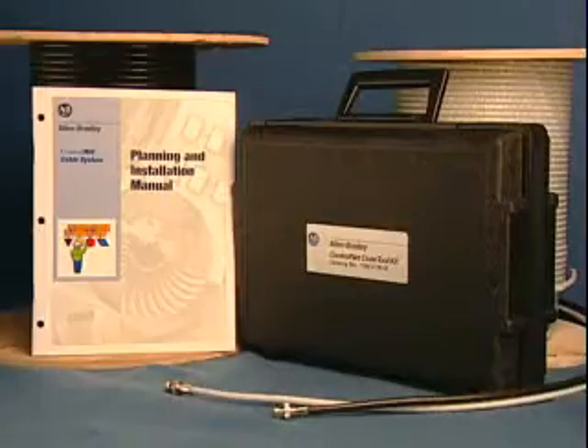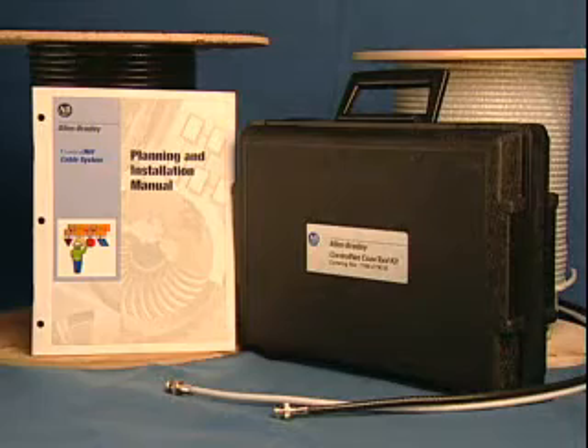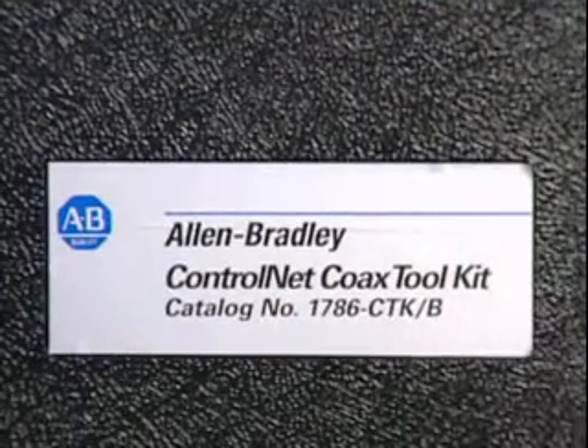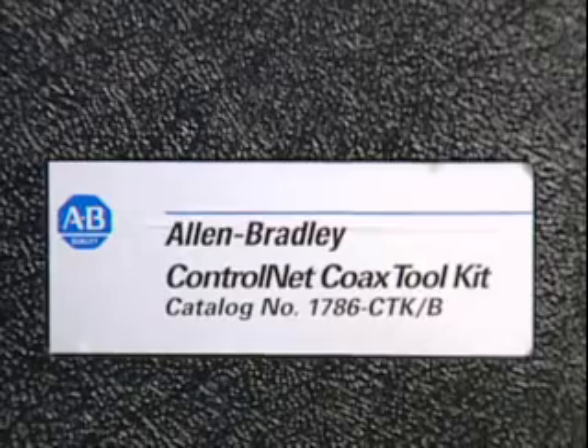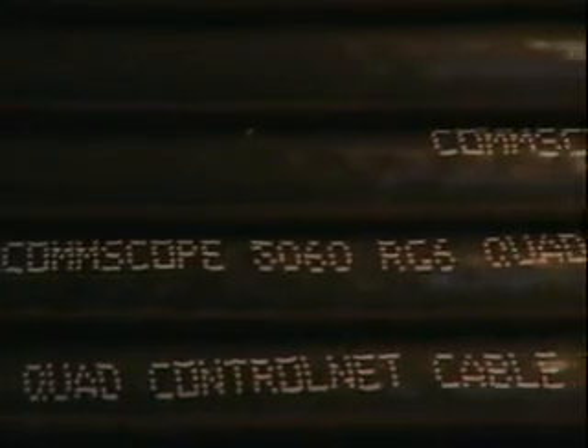As an authorized manufacturer of cable for Allen Bradley, we'd like to demonstrate the proper connectorization procedures for ControlNet cable. We will be using the Allen Bradley ControlNet Toolkit, catalog number 1786-CTK/B, and CommScope non-plenum ControlNet cable, catalog number 5060, and plenum ControlNet cable, catalog 5061.